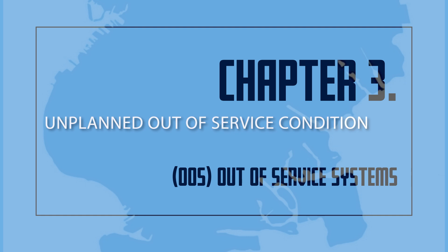Unplanned out-of-service condition: A serious defect in the sprinkler system including but not limited to an empty tank, a break or major leak in the system's water piping, inoperative or shut water supply valves, defective fire department connections, construction-related shutdowns affecting more than one floor, or complete or partial shutdowns of the sprinkler system other than a shutdown for a planned removal from service.